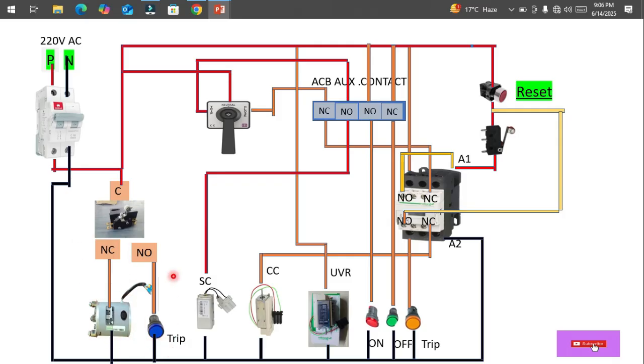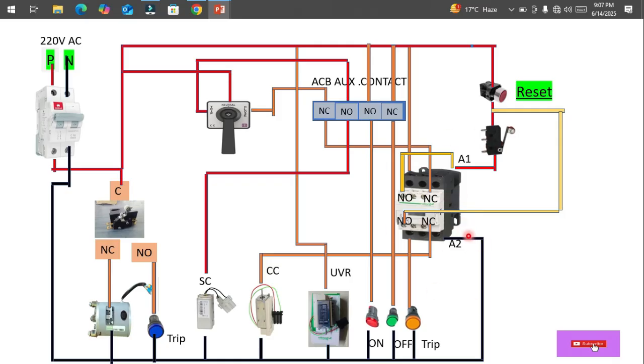Another component is the TNC switch, where we have Trip, Neutral, and Close. This is for locally operating the ACB — you can control it from this TNC switch. The next block is the auxiliary contact, which is a block inside the ACB. We can take the status of the ACB from this and use it to operate the ACB. This contactor is also an auxiliary contact used in the trip system.